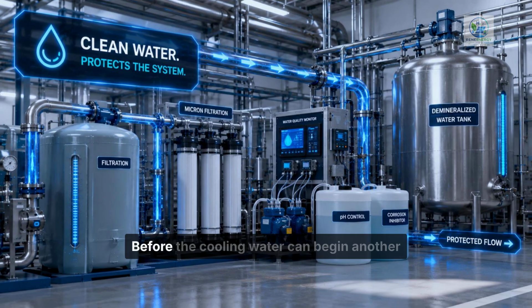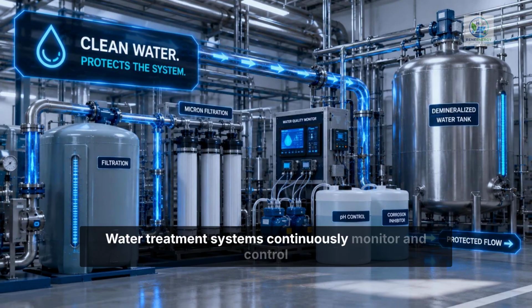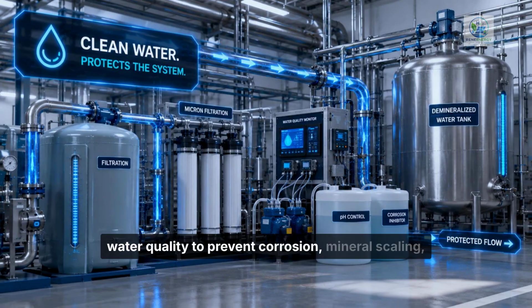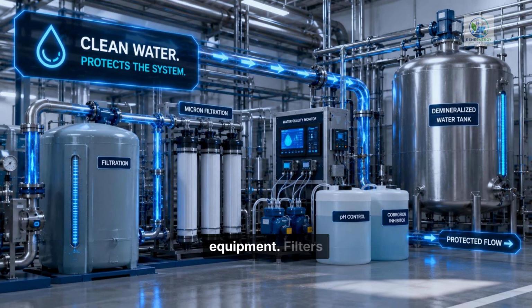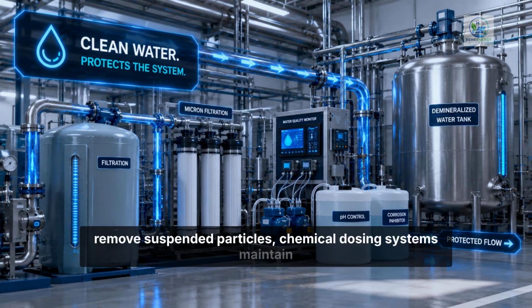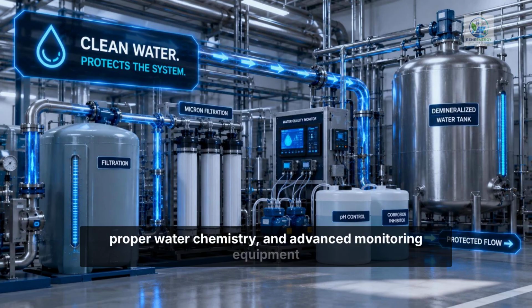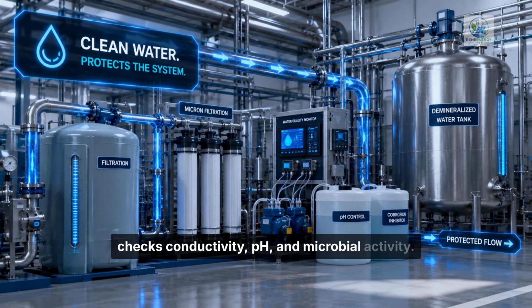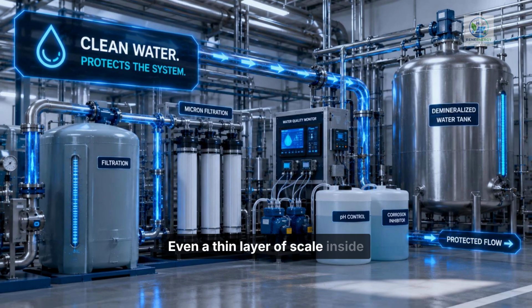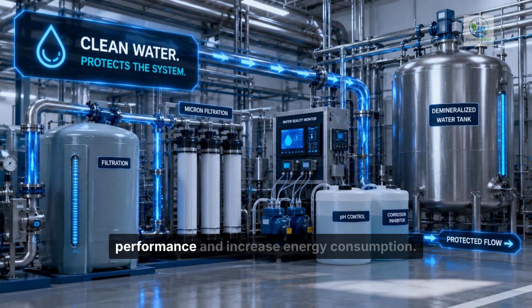to the open air. Before the cooling water can begin another cycle, it must be carefully maintained. Water treatment systems continuously monitor and control water quality to prevent corrosion, mineral scaling, biological growth, and contamination inside the cooling equipment. Filters remove suspended particles, chemical dosing systems maintain proper water chemistry, and advanced monitoring equipment checks conductivity, pH, and microbial activity. Even a thin layer of scale inside a heat exchanger can significantly reduce cooling performance and increase energy consumption. Clean water isn't simply a maintenance concern, it is a critical engineering requirement that protects billions of dollars of AI infrastructure while ensuring the entire cooling system continues operating efficiently for years to come.